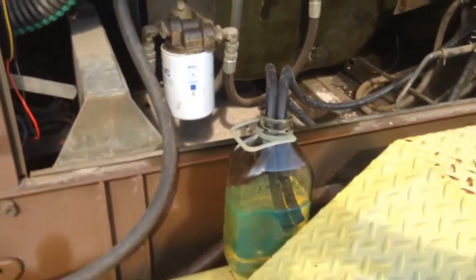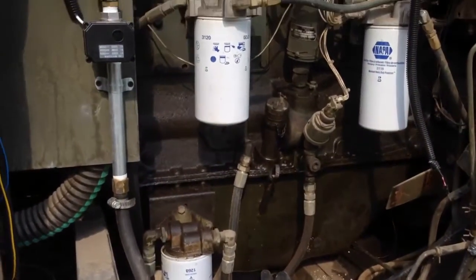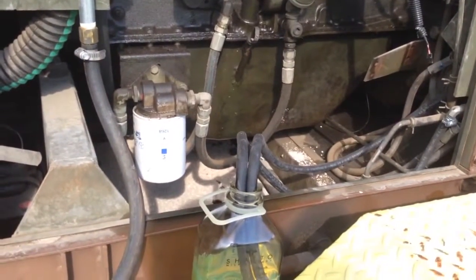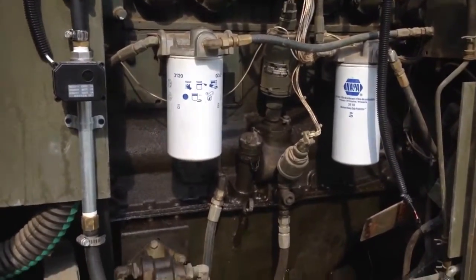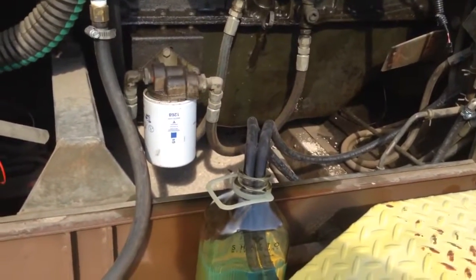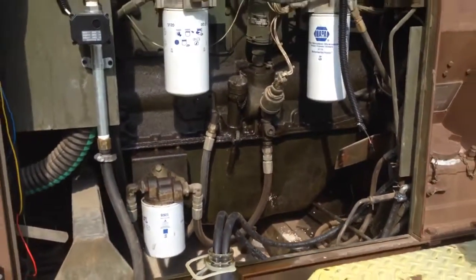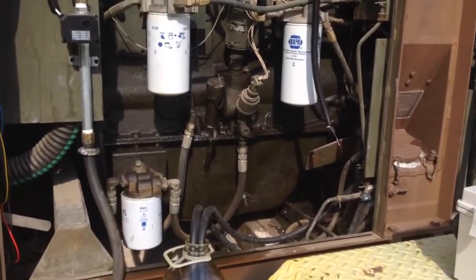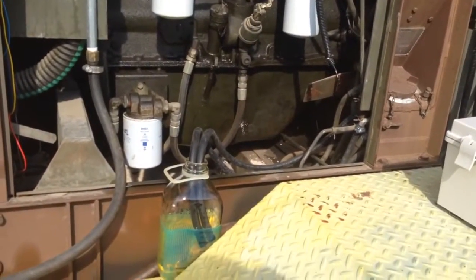We're kind of limited as to the pressure we get here from the local gas company to get enough pressure to actually run. This is such a big generator, 30 kilowatts, that it takes a little bit higher service pressure to hit the 70-30 ratio, but 50-50, hey, I'm happy with that. That's a good ratio. We normally shoot for 70-30, but for this demonstration, hey, it'll work out great.